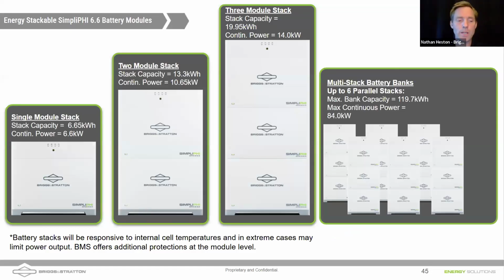It uses superior LFP chemistry. We've been developing intellectual property on LFP battery chemistry since 2010. And I know the industry has moved our direction on this, but for 15 years, we've been perfecting LFP battery chemistry. You're looking at the power output ratings for this battery. A single 6.65 kilowatt hour battery has a power output rated at 1C at 6.6 kilowatts. There are some reductions that occur from the battery controller and our need to keep the batteries balanced in terms of power output. But a two stack of batteries can output 10.6 kilowatts of power. So a lot of good power output there.